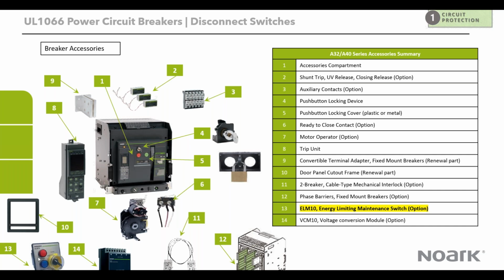The other important accessory here is the trip unit, obviously. That's what gives you the protection. We've got them in LI, LSI, and LSIG. We have the basic trip unit, we've got the ammeter, and also the advanced one, which we call the harmonics type, that allows you to measure the current and the voltage. You can also monitor the harmonics in the system as well. So that's in a nutshell what we are able to offer as NOARK.